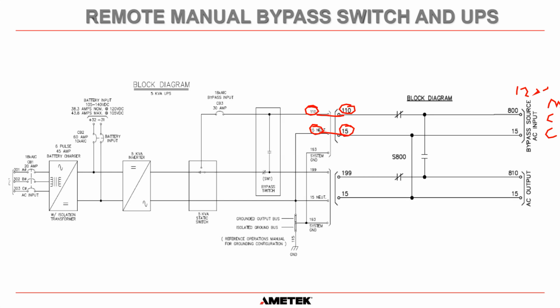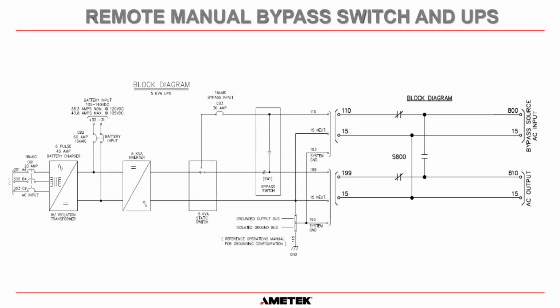Now what happens is the bypass is going to go in here and it's going to be available at the static switch. And then the output of the UPS is wire 199. That connects to wire 199 in the MBS. Power from the output of the UPS is going to go through the RMBS and out to your load this way. Then if we move this RMBS to the bypass position, this is going to open, but before that opens, this closes, and it allows bypass power to go down through that switch and out that way, and then it will open this contact and the UPS is no longer supplying power.